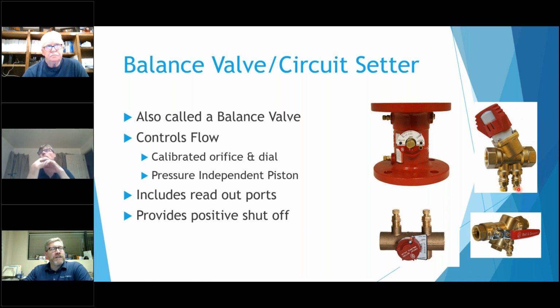This one here is kind of a step up. This is an automatic manual type balance valve. It's our flow setter. Basically, this dial up here has a GPM reading on it where you can go in there and set, I want 1 GPM or 2 GPM, and whatever pressure is coming into this will not change that flow. It will always just maintain 1 or 2 GPM, whatever you have it set for up here. But it is adjustable, so there is a range on each one of these valves.